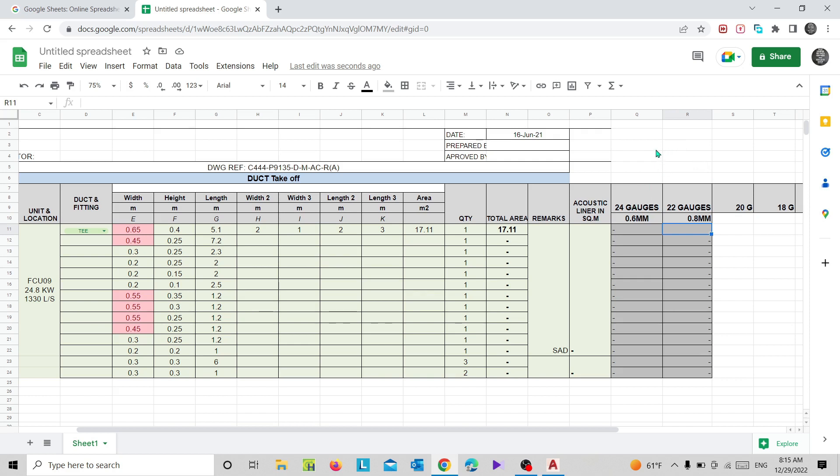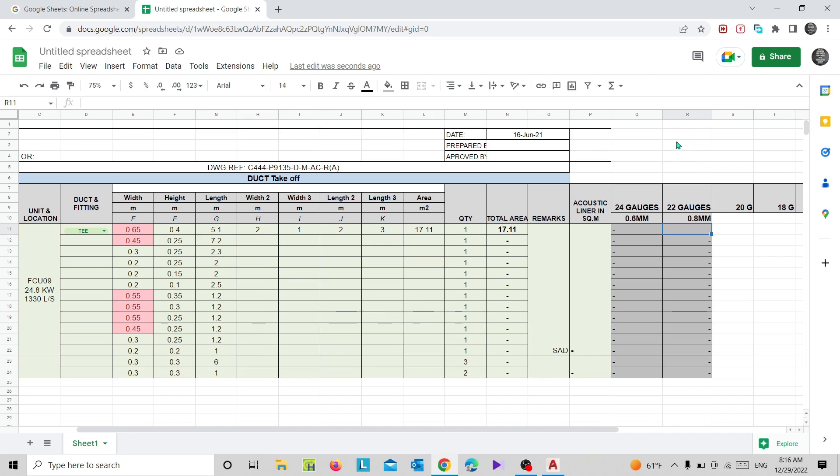For example, when it comes to DW, the duct gauge for 24 gauge is 0 to 400mm. So 0 to 400mm duct sizes we will use this 24 gauge duct. 400 to 800mm duct sizes we will use 22 gauge duct. You can refer this chart from SMACNA or DW 144. You can download it from the internet, or if possible I will attach it to this sheet and you can easily refer it.